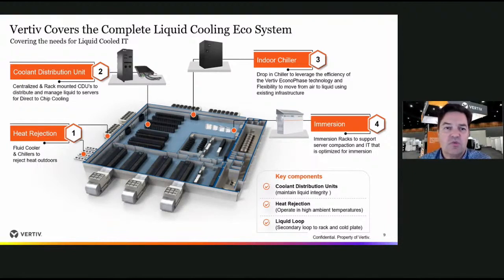Certain devices will need chilled water. Can we deliver that precisely and effectively in terms of flow rate, pressure drop, as well as increased heat demand effectiveness for these devices? Whether we're deploying a rear door, a direct-to-chip device, or an immersion cooling system, we have the flexibility to deliver the necessary water rate, water type, as well as flow and pressure for those devices.